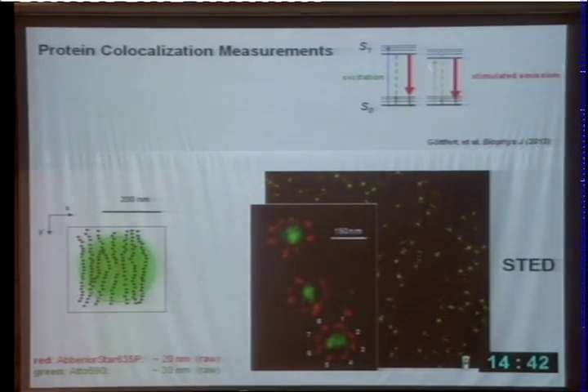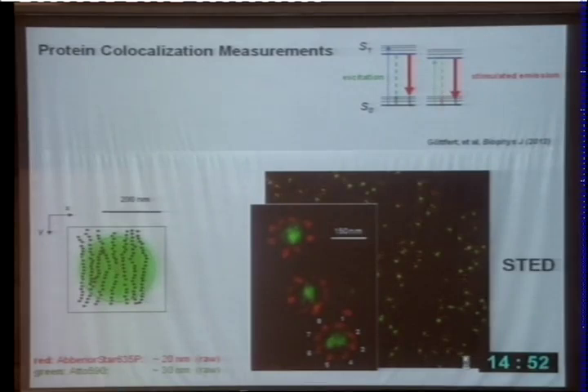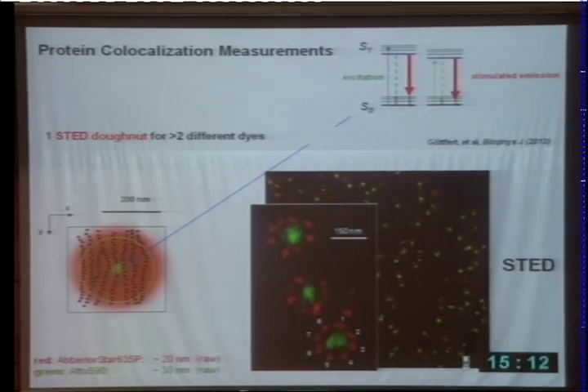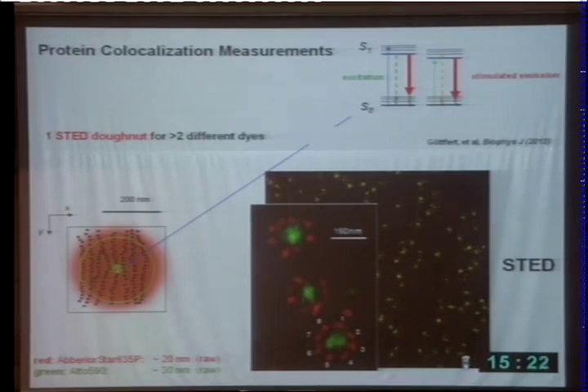A technical remark: different dyes have different excitation spectra, but you can often excite two different dyes with one wavelength. The same applies in many cases to STED — you can use one STED wavelength to turn off several dyes if they are not spectrally too distinct. In this recording, we use just a single laser at 775 nanometers to silence two dyes, achieving about 20 nanometer resolution in one channel and 30 nanometer in the other. Because both dyes are silenced simultaneously, you have perfect co-localization, since the position of the emitter is imprinted by the donut zero.